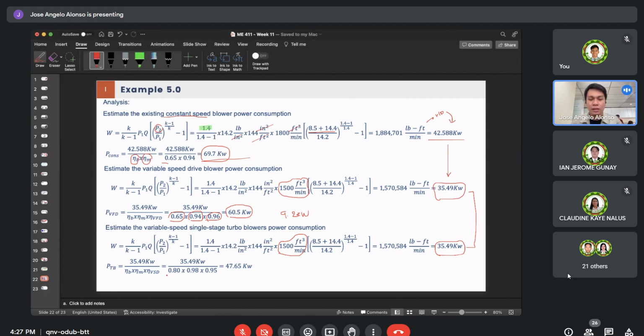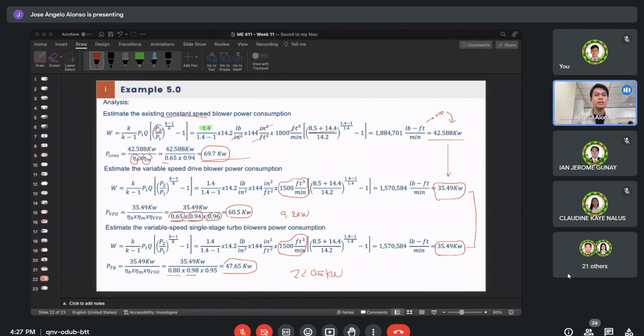The blower efficiency is 0.8 compared to 0.65 for our existing blower. Motor efficiency is 0.98 compared to the existing motor efficiency of 0.94. So the power consumption of the turbo blower is 47.65 kilowatts. 69.7 minus 47.65 gives us a savings of 22.05 kilowatts when we install turbo blowers compared to our existing constant speed setup. That's quite significant, right? It's a great deal in terms of power saving.